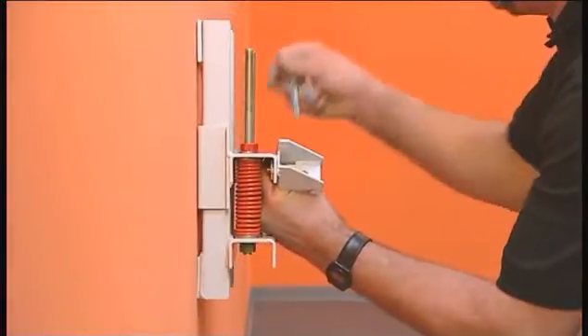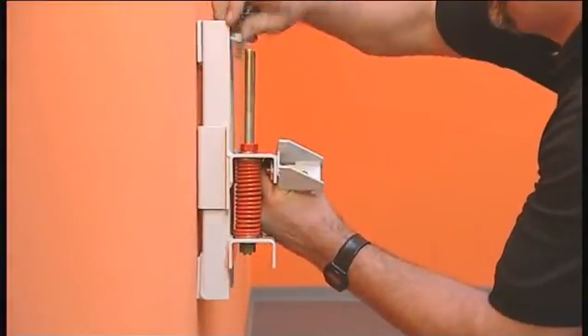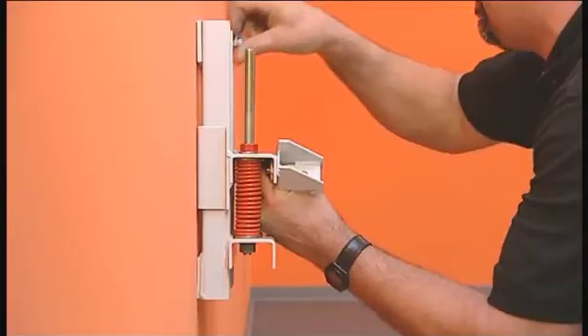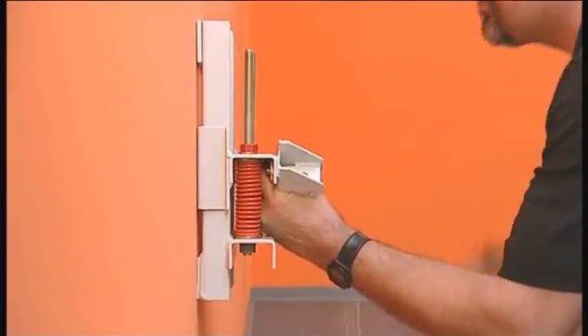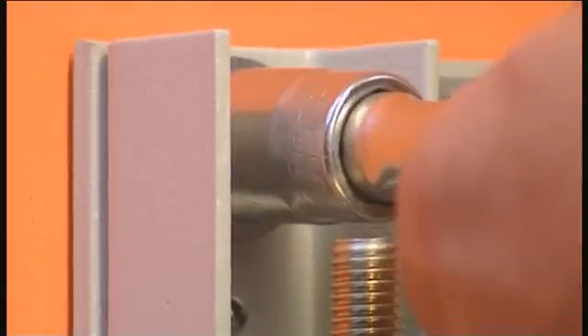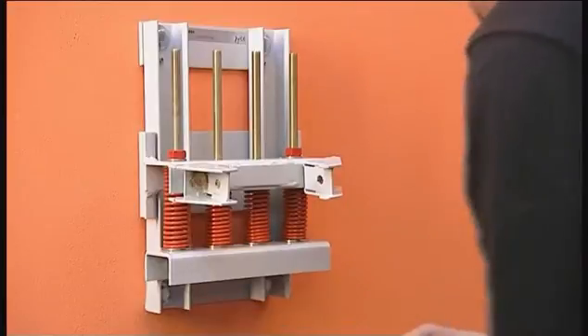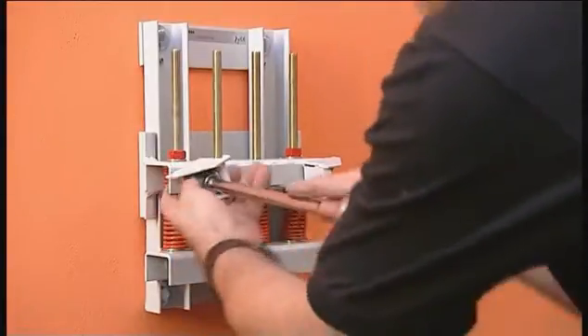For vertical installations typical in large multi-story buildings, the trunking system is installed with spring brackets. Their attachment to the wall is the first step in the installation procedure of the LX system. The spring brackets bear and compensate for the weight and load-dependent elongation of the trunking units.